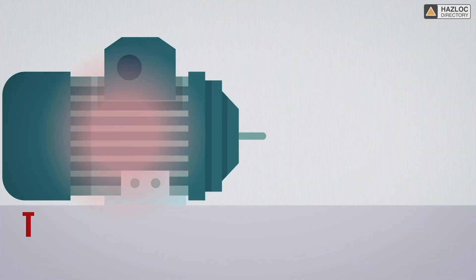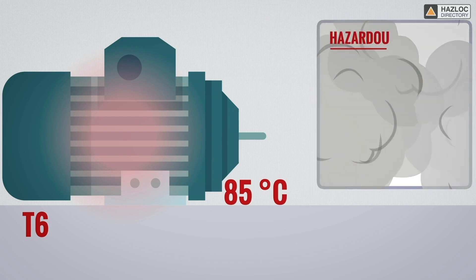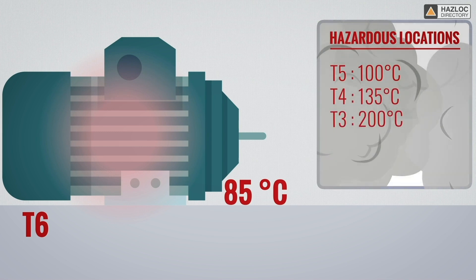All equipment with a T6 rating which has a maximum surface temperature of 85 degrees Celsius can be also used in T5, T4, T3, T2, and T1 environments.